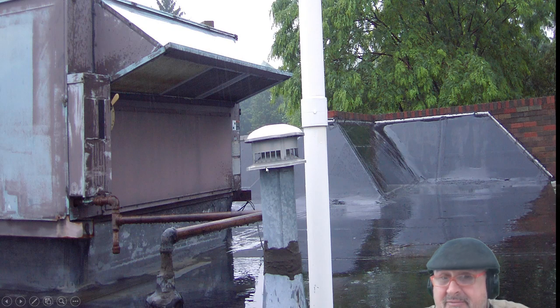That's bad enough, but then they had this thing venting up on top of the roof, and guess what was right above it — the cold air return. Carbon monoxide gets sucked into the air, and everybody's getting nauseous. The real problem wasn't the vent placement itself — if the water heater didn't have incomplete combustion, this setup would be fine. But 1 out of 50 water heaters has incomplete combustion, and that's okay as long as the gases vent outside. If you bring them back in, or there's poor drafting, you've got a whole other problem.